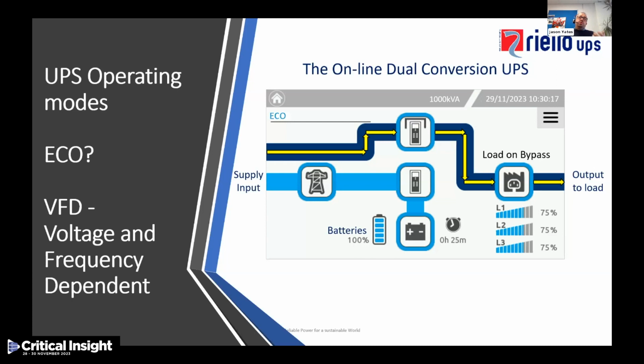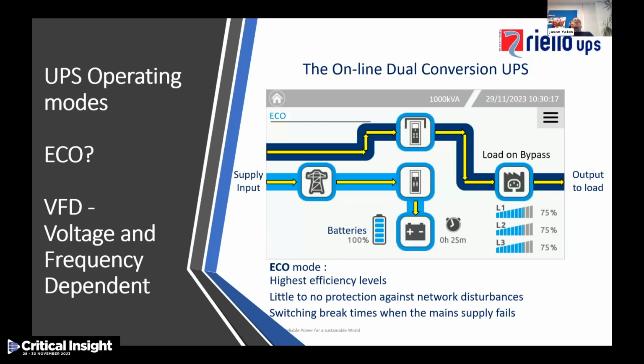And because we're not performing those two conversions, we haven't got the same losses through the UPS system. So a typical UPS of this type can be running at up to 98.5, 99% efficiency, albeit there is a downside to this, which I'll come to in a second. We are still performing some conversions because we're still taking AC power in, because we've still got to maintain the batteries and the systems within the UPS system. So things are still running in the background, but eco mode provides the highest levels of efficiency.